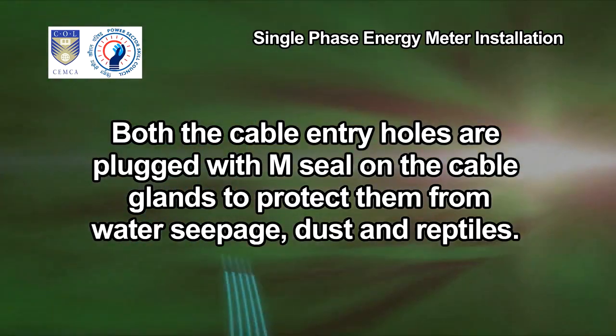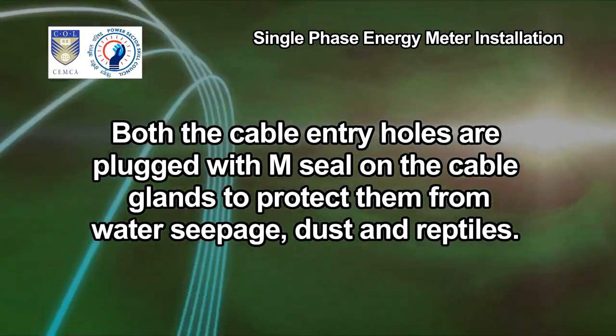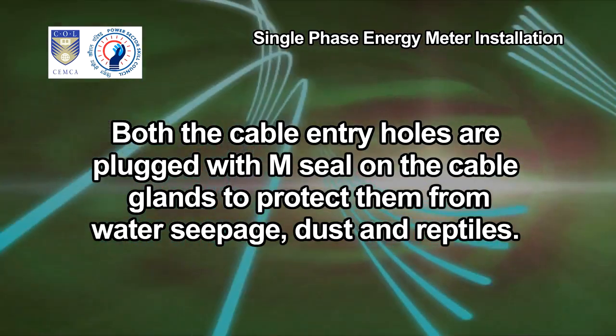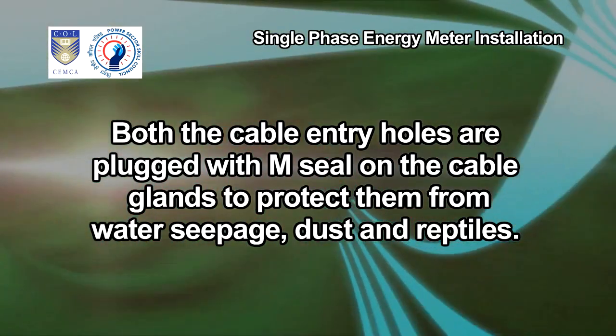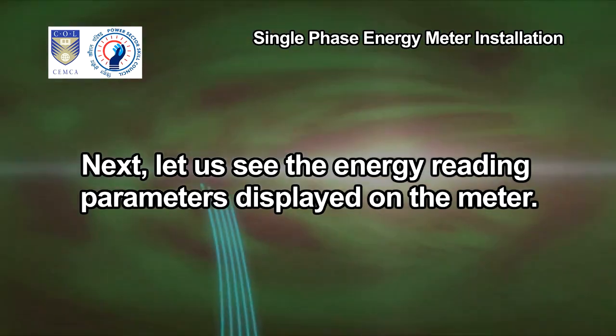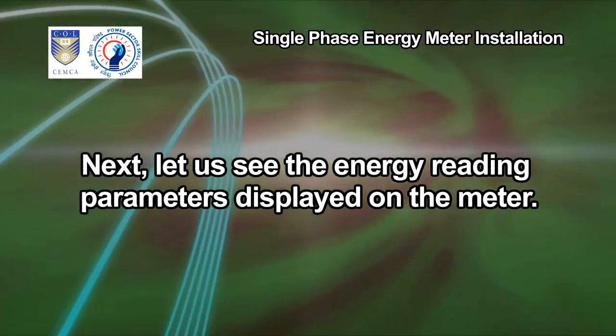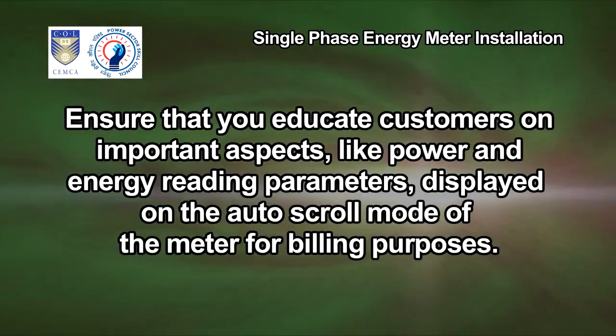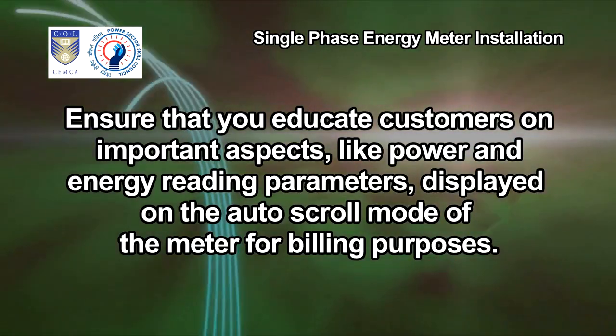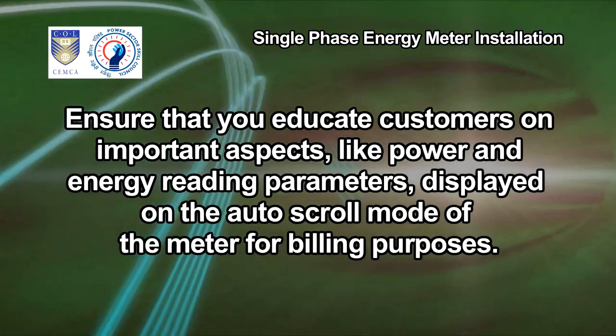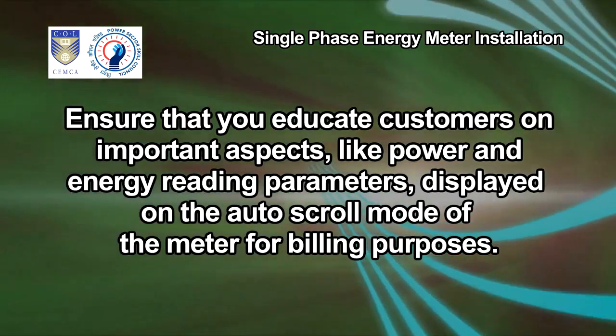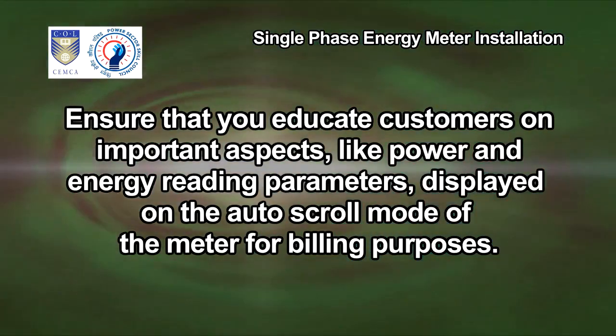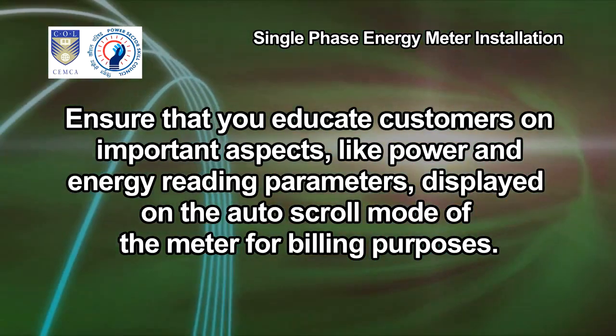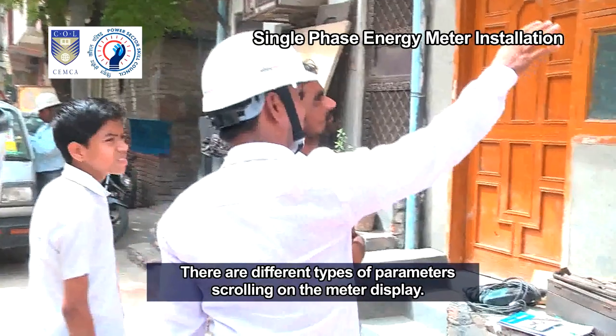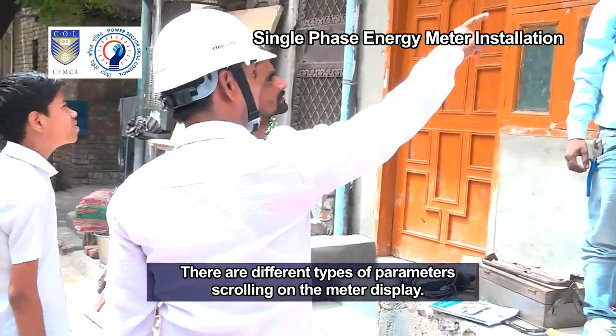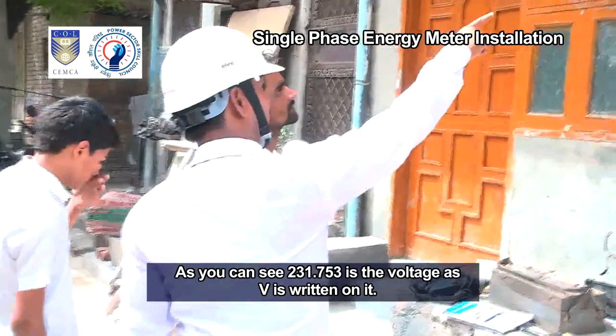Both the cable entry holes are plugged with M seal on the cable glands to protect them from water seepage, dust and reptiles. Next, let us see the energy reading parameters displayed on the meter. Ensure that you educate customers on important aspects like power and energy reading parameters displayed on the auto scroll mode of the meter for billing purposes. There are different types of parameters scrolling on the meter display.